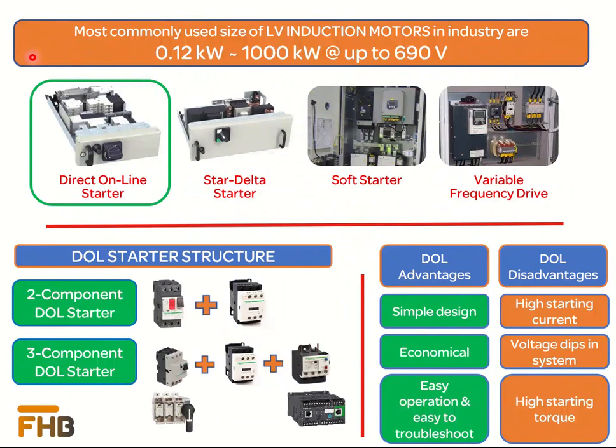The most commonly used sizes of low voltage induction motors are in the range from 0.12 kW to 1000 kW and from 400 volts to 690 volts. Different starting techniques are used in industry for induction motors, like the DOL starter, Star Delta starter, soft starter, and motor starting using a variable frequency drive. Our today's discussion is on the DOL starter.